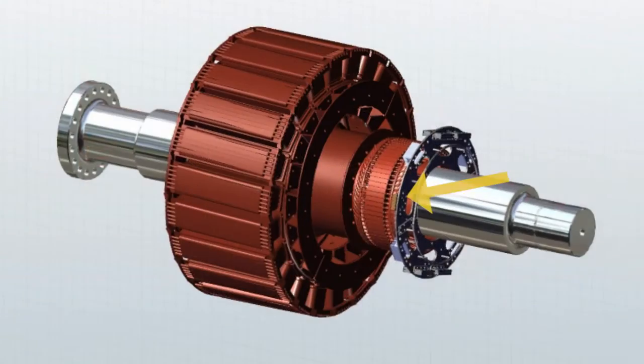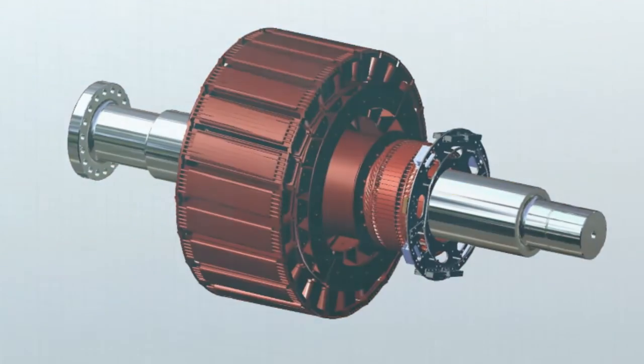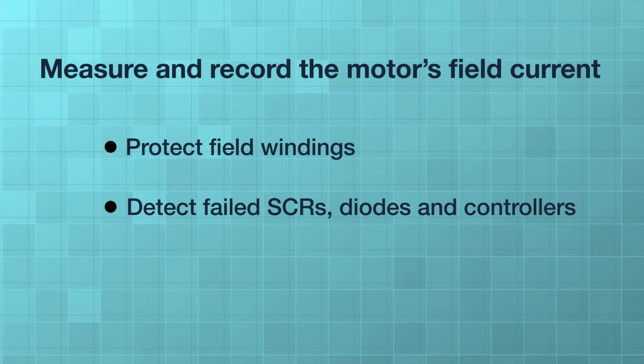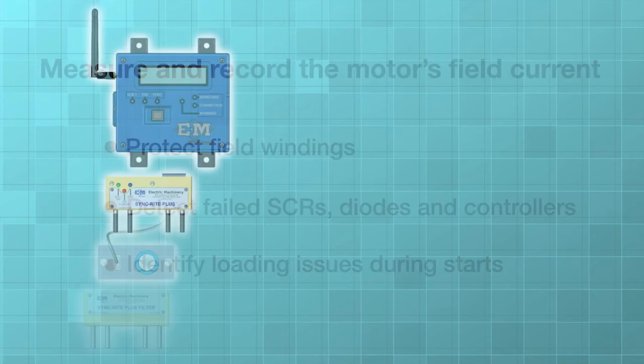By placing the Sync-Rite Plus current sensor on the rotor, you will be able to measure and record the motor's field current remotely. This allows you to protect field windings, detect failed SCRs and controllers, and identify loading issues during starts.